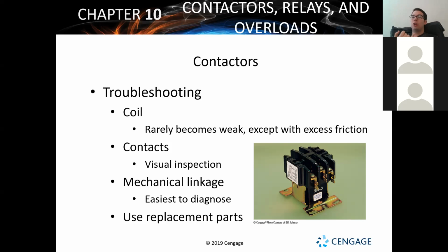The other thing that causes this is something called arc welding. If a system short cycles, trying to come on multiple times without any safety kicking it off or putting it into a delay, it just kicks on, doesn't work, kicks on again, doesn't work, over and over. That's a very bad thing to happen to a system. When that happens, the contactor opens and closes rapidly, and doing that quickly can make the spark get so hot that the metal actually welds together, arc welds, and the contactor remains closed.